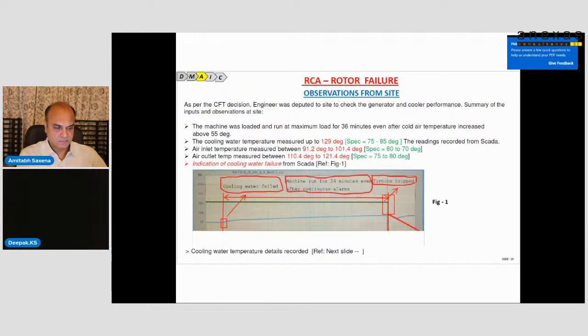Yes, our engineer was deputed to site to check the generator and cooler performance. Summary of the inputs and observations at site: when he went to site, the machine was loaded and run to maximum load for only 36 minutes, even after the cold air temperature increased above 55 degrees. When the machine was loaded to maximum load, the cooler water temperature measured up to 129 degrees. The specification should be 75 to 85 degrees.